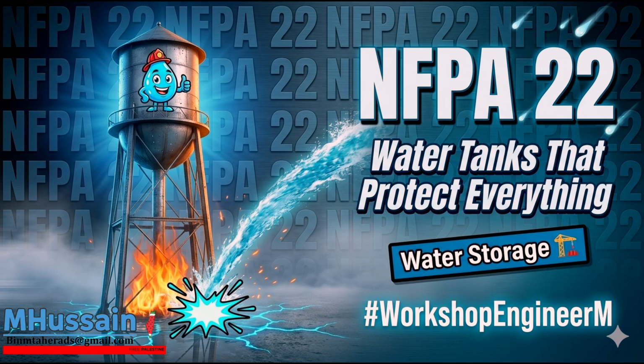What happens if your math dictates you need a starting pressure of, let's say, 200 psi to push all the water out? Then you have a major conflict with your downstream components. Because they can't handle that pressure. Right. If the holding pressure required in the tank exceeds the maximum pressure rating of the other components in your fire protection system, like the butterfly valves, the alarm check valves, or the sprinkler heads themselves. Which are often only rated for 175 psi? Usually 175 psi, yes. If your tank needs 200 psi, you cannot build the system. You cannot intentionally overpressurize the downstream network.